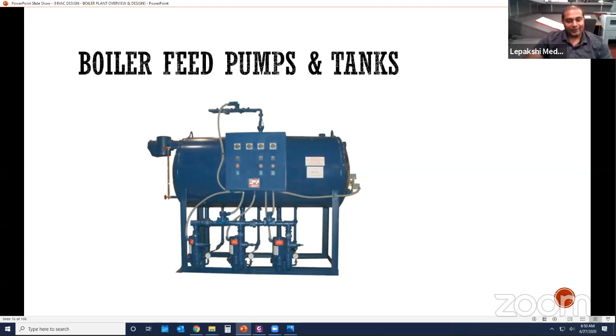So we talked about the combustion, we talked about the exhaust, right? So now let's talk about something else. What is boiler feed? Boiler feed is, as the name says, it supplies the water to the boiler. The boiler keeps on converting water to steam, so the quantity of water is getting less and less. So it's got to be topped up with water again. That's the purpose of this boiler feed. Again, you have to design the sizing. The moment you're putting in equipment, you have to size it properly. This is how you're going to size the boiler feed tank, how big the tank is going to be.